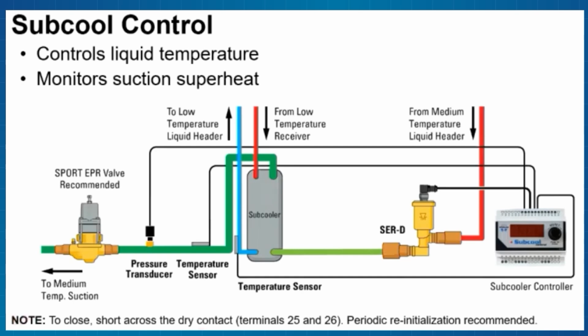We can do this a lot of different ways. The simplest is this suction header and this liquid go to the same rack as this. Same suction, same liquid. If I do that, I get all the advantages of a mechanical subcooler except the energy savings, because every BTU of work this rack is doing, it's doing to itself. Same suction group. It says minus 27 and my EPR is set at 47. I'm doing that work at the same suction, minus 27. That's what my compressor has to achieve for that rack. I don't get any energy savings, because my compressor still has to run at minus 27.